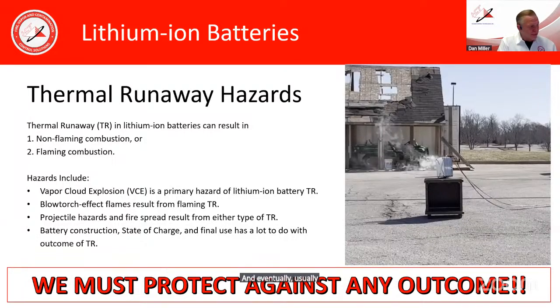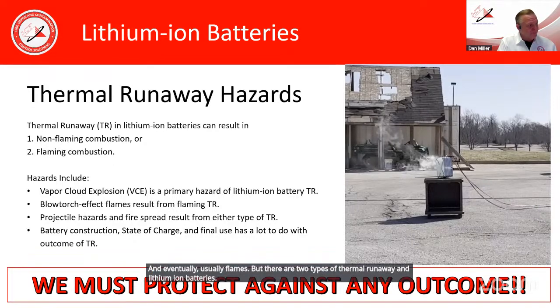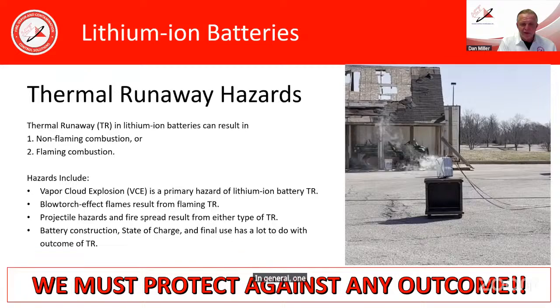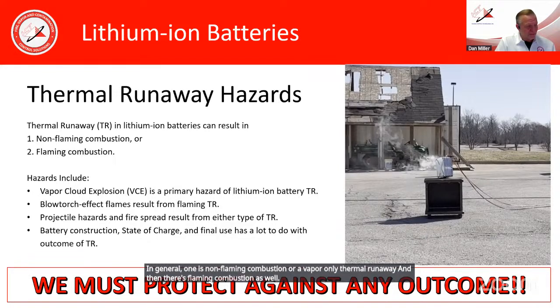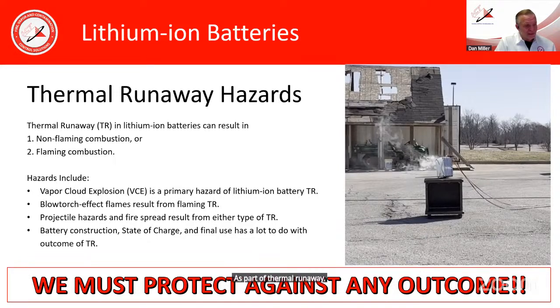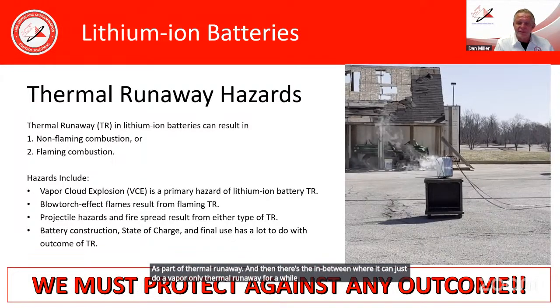There are two types of thermal runaway in lithium ion batteries in general. One is non-flaming combustion, or a vapor-only thermal runaway. Then there's flaming combustion as well, as part of thermal runaway. And then there's the in-between, where it can just do a vapor-only thermal runaway for a while and then it finds an ignition source, or it gets hot enough internally to cause flaming.